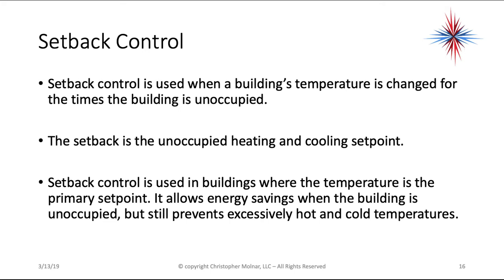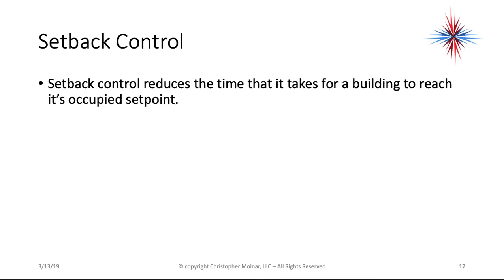Set back control is used when a building's temperature is changed for times the building is unoccupied. The set back is the unoccupied heating and cooling set point. It allows energy savings when the building is unoccupied but still prevents excessively hot and cold temperatures. Set back control also reduces the time it takes for a building to reach its occupied set point — rather than turning a system off completely, we change the temperature to reduce the heating or cooling needed when the building becomes occupied again.